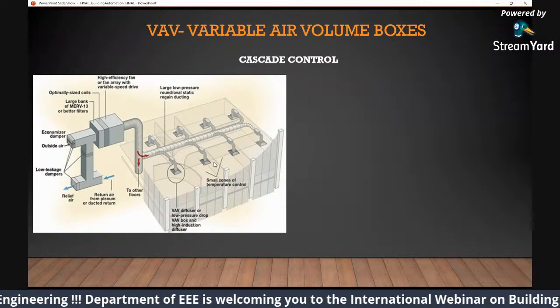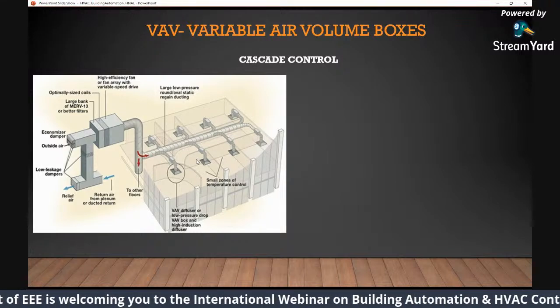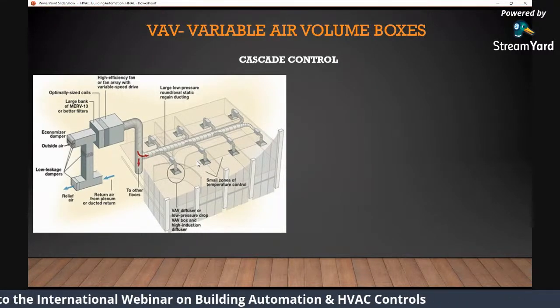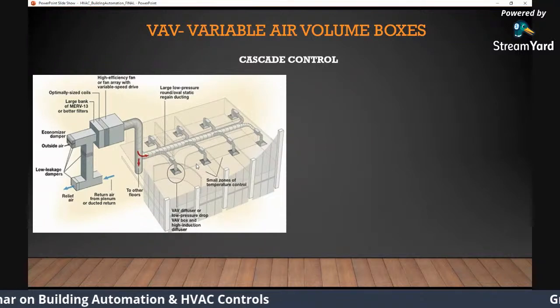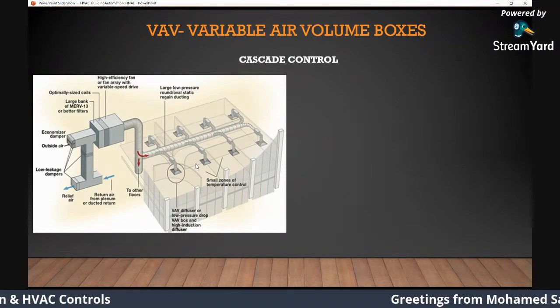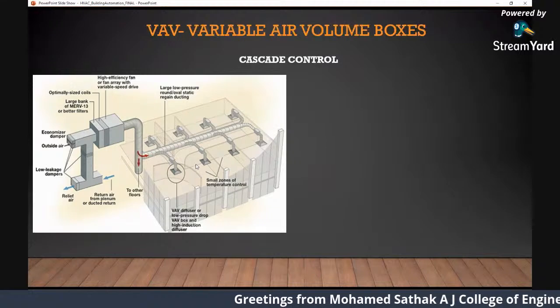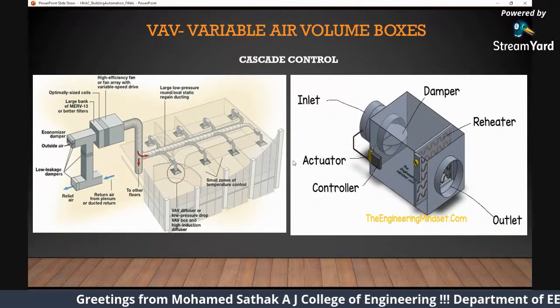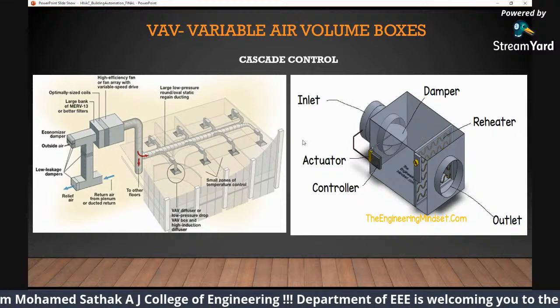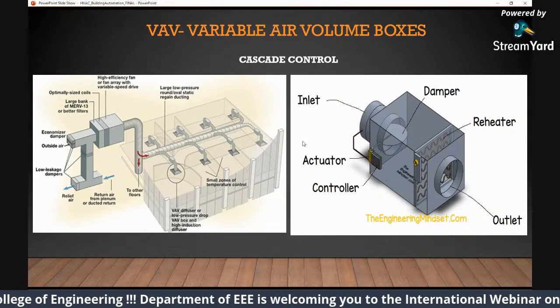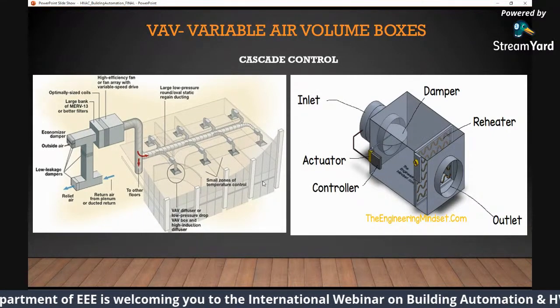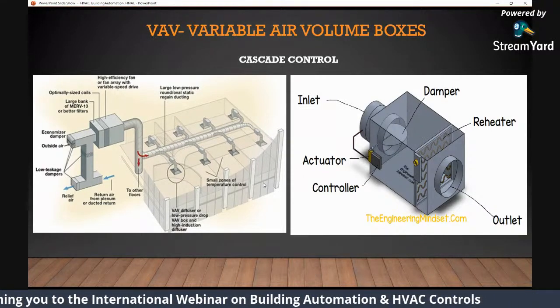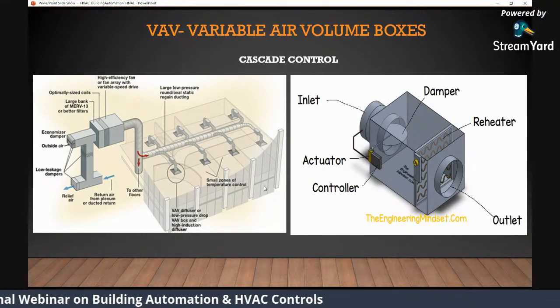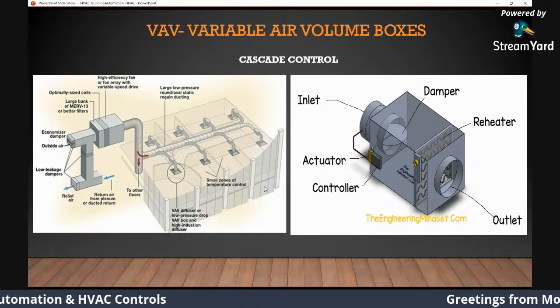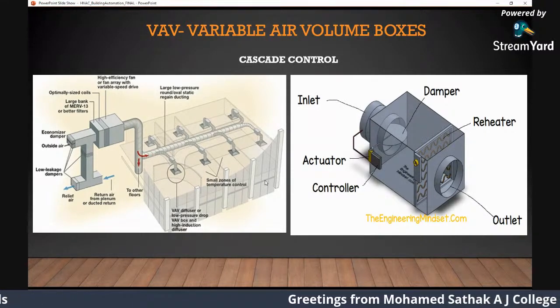Now, how do the other rooms in a building get ventilated? This is another nice picture which shows the purpose of a VAV box. There are two major terminal units. Fan coil units are one, an independent mini AHU, and the other unit is called VAV boxes, or variable air volume boxes. The only purpose of this unit, a small box which has a damper in it, is to save air. This box gets air from the AHU. Let's say there are 10 floors in a building and each floor has 10 rooms. The AHU supplies air to each floor, and each room will have a variable air volume box.